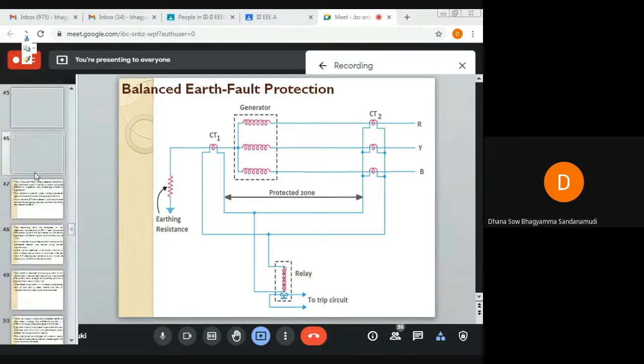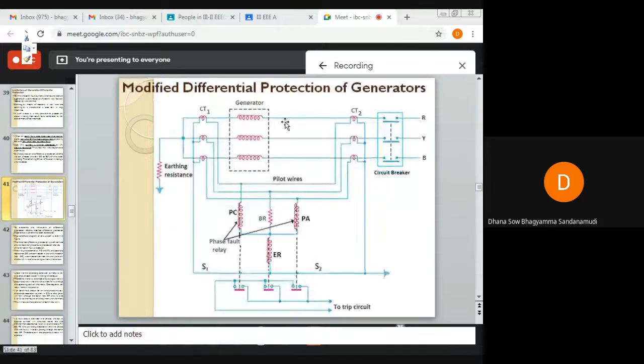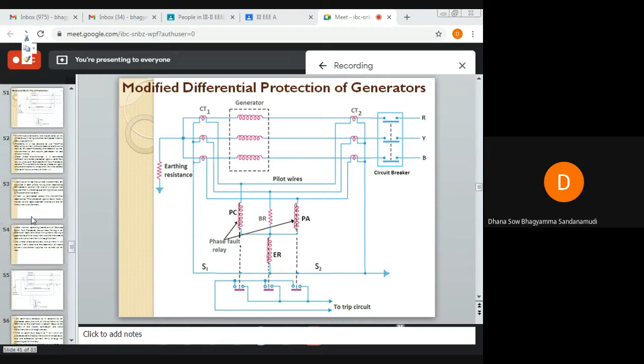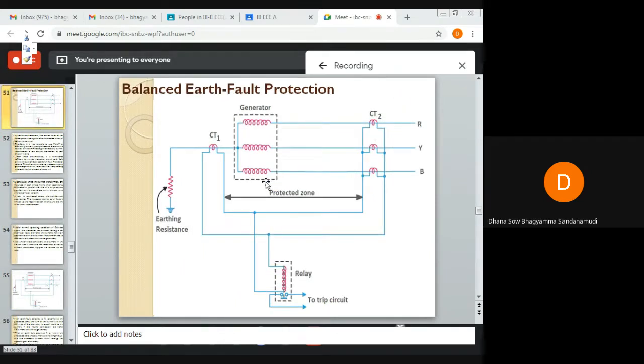Why? Because if you observe here, this is the generator three-phase winding, and you can see the neutral point is far away from this winding. When it is a big size generator, when the size of the generator is large enough, there will be sufficient space for the CTs to be connected towards the neutral side as well as on the other side of the winding. Whereas in a small size generator, the neutral ends of the three-phase windings are often connected internal to a single terminal. Therefore it is not possible to use the Merz-Price circulating current protection, because there is no possibility of accommodating the necessary current transformers.